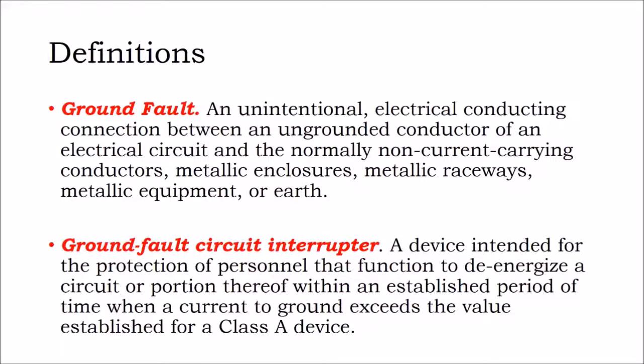Ground fault: an unintentional electrical conducting connection between an ungrounded conductor of an electrical circuit and the normally non-current carrying conductors of metallic enclosures, metallic raceways, metallic equipment, or earth. In other words, whenever you have an ungrounded conductor, that's a conductor at high voltage, and then it connects to that non-current carrying metal conductor, and it faults and that current connects to ground.